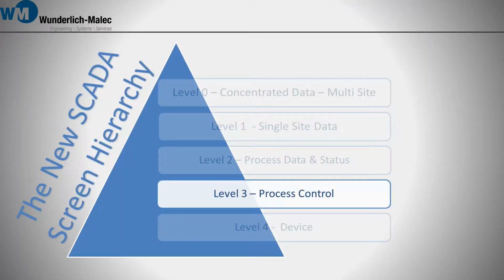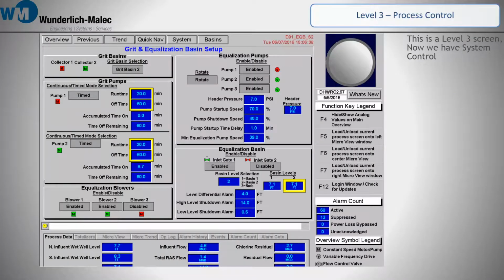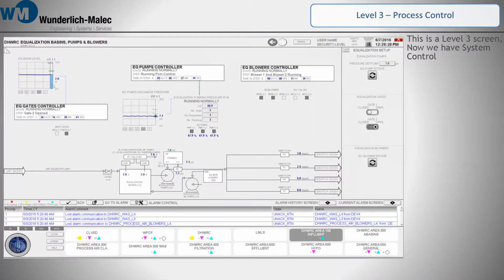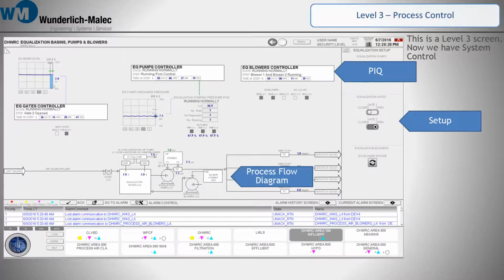Level 3 is for control and is optimized by providing more intuitive data and system health. Conventionally, for system control, the operator had to navigate down to the device level and then open the setup screen. Situational awareness combats this by removing that extra step and instead providing control at Level 3. The process flow diagram appears at this level because it may be useful to the operator to have a visual layout of the system. The right side of the screen is reserved for what was the current setup screen. Here the operator can input set points, enable equipment, or select different modes. But the PIQ is the brains and it controls each process.